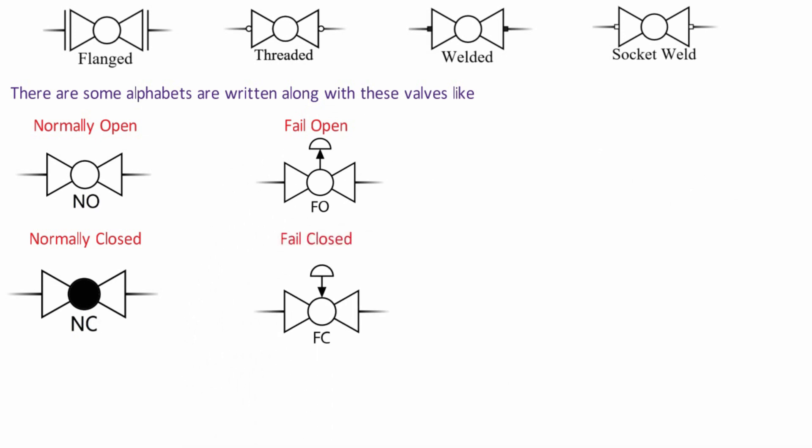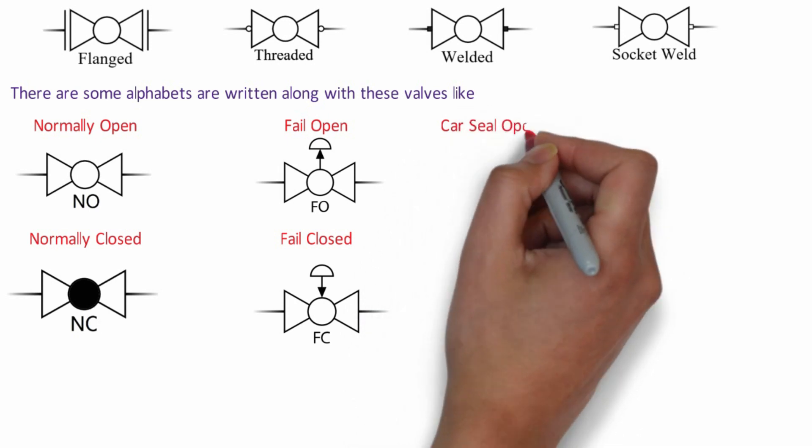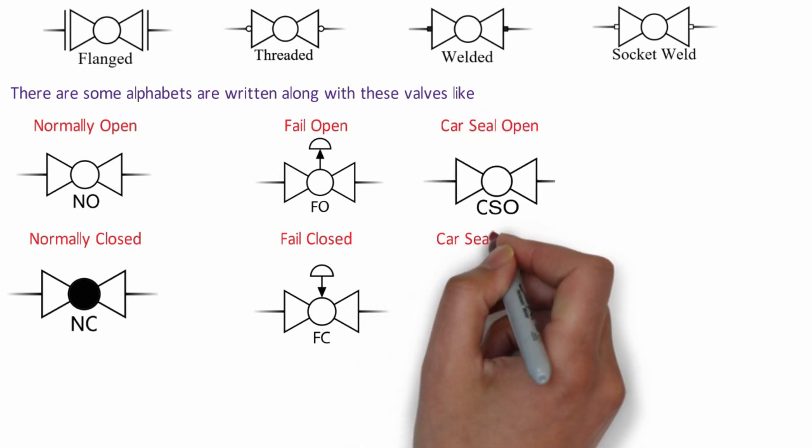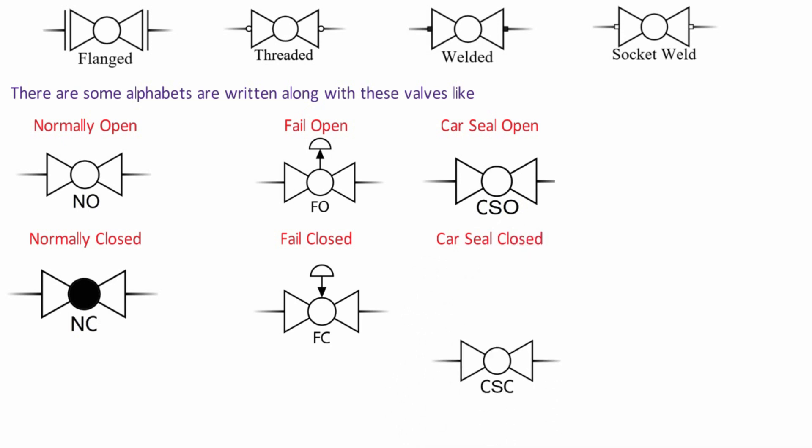Fail open or fail close valves would open or close at a loss of signal or power. These types of valves require air pressure to stay open or close. CSO-CSC, Car seal open and car seal close. Simple device is used to lock or seal the valve in open and close position to prevent unauthorized operation of valve.